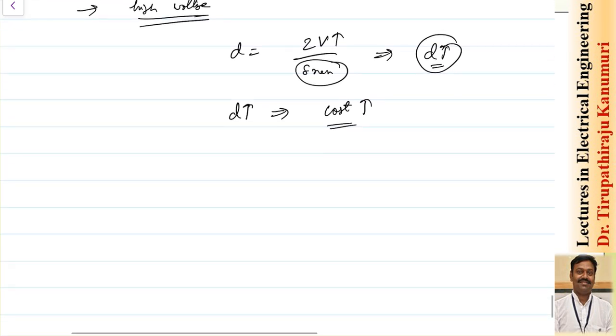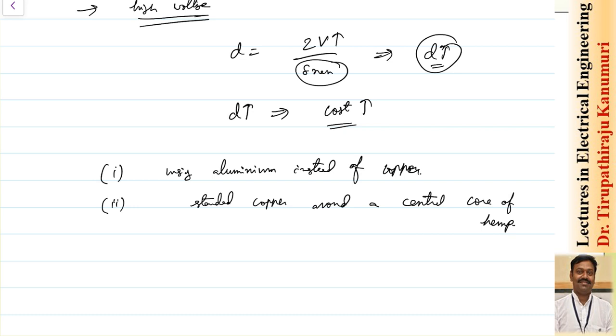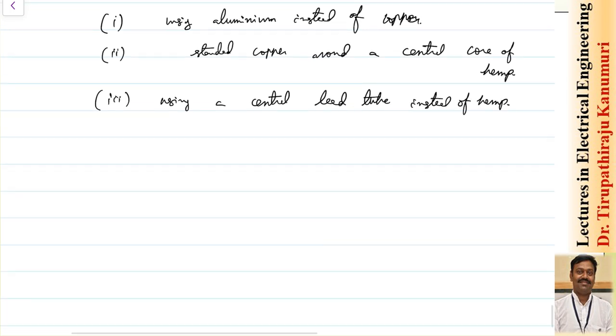The techniques to increase the effective conductor diameter are: first, use aluminum instead of copper — aluminum requires a larger cross-section for the same conductivity, or use ACSR/stranded aluminum conductors; second, for copper, strand the conductor around a central core of hemp to increase diameter; third, use a central lead tube in place of hemp at the center.